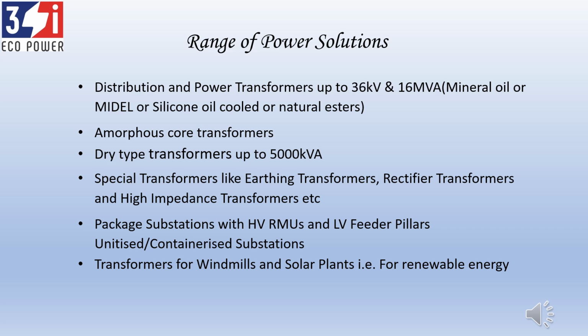For dry-type transformers, we import coils and assemble them at our factory. We supply many shopping malls in and around Chennai with added switchgear, making them package substations. We also make special transformers like earthing transformers, rectifiers, high impedance transformers, etc., even Scott-connected transformers for railways, and open delta transformers for any specific design requirements.